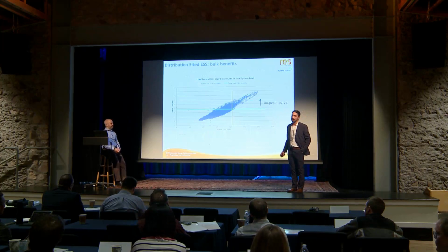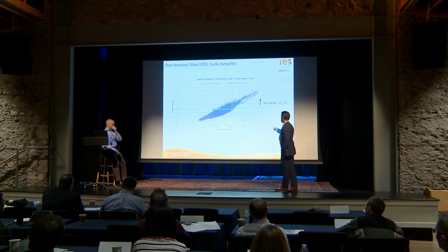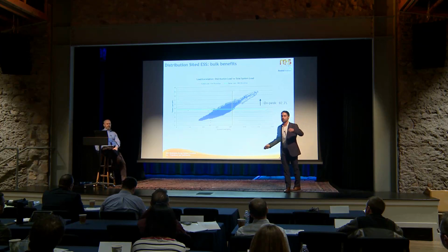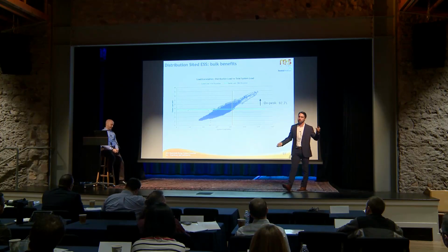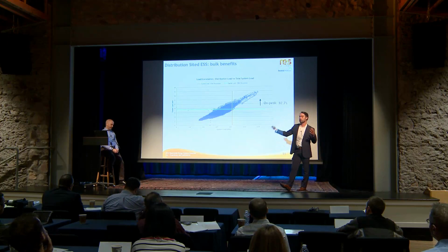Yeah, exactly. I mean, at this top region here, that means your feeder load is peaking - it can't regulate, it can't charge anymore, because then you're going to overload the transformer at the distribution site. So you either can only regulate up, or you have to take it out of the frequency regulation market altogether. So you can't do frequency regulation.